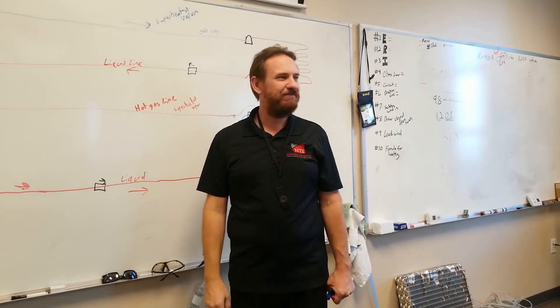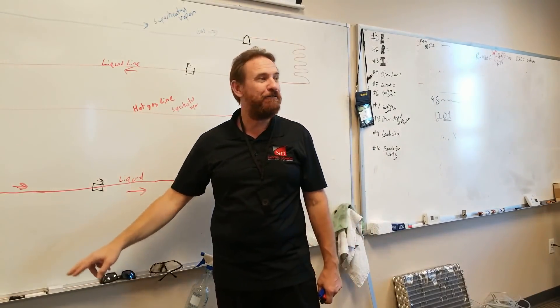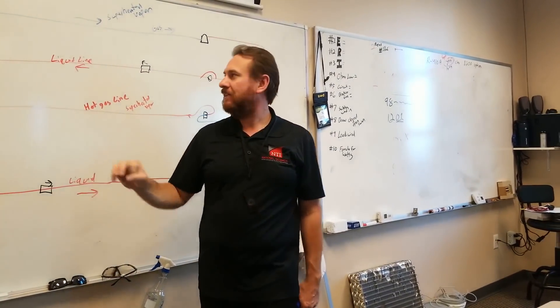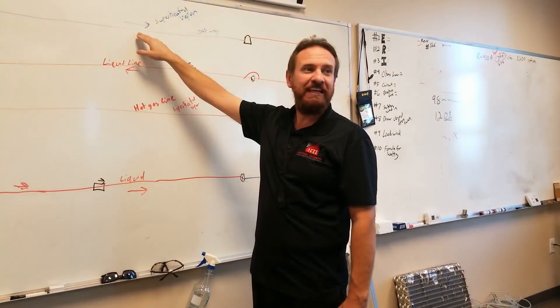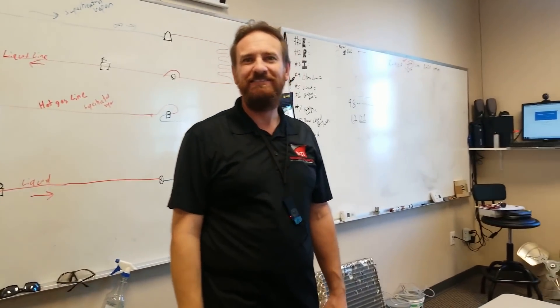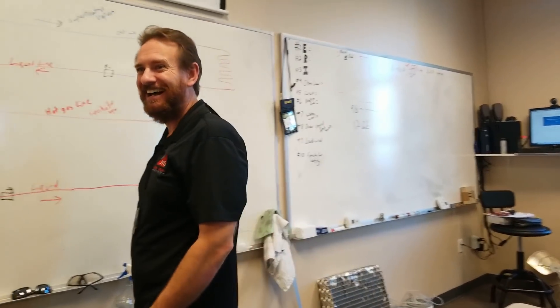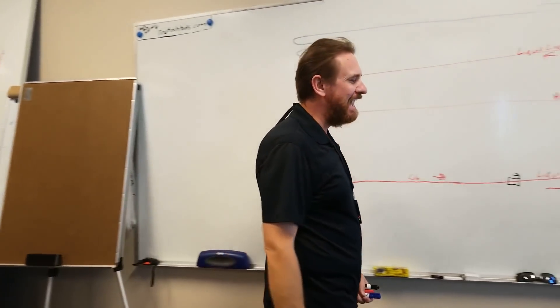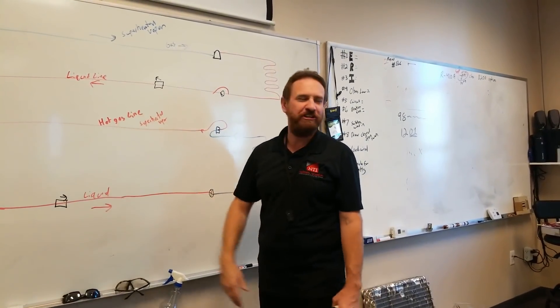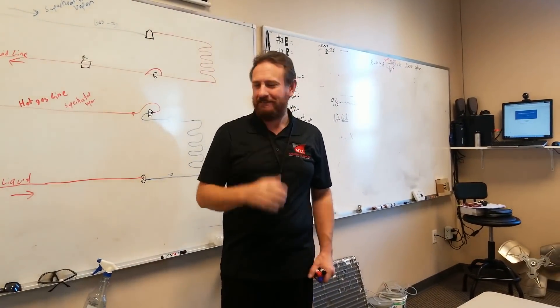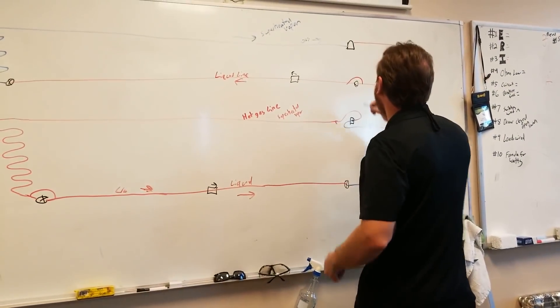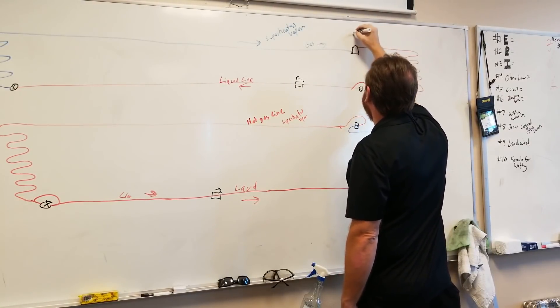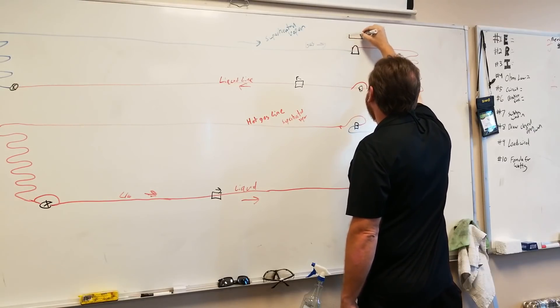Does that make sense? Isn't it cool? This line is still the liquid line — the refrigerant is flowing the opposite direction, but it's still liquid. That three-eighths line is still liquid. This bigger fat line — it's still gas here and still gas here, no matter what. There's a reason that was drilled in earlier, and this is why. So let's add some components so that we don't have to go and recover all that refrigerant and change all these components all the time. We're going to add a valve — a reversing valve — because it's going to reverse the flow of refrigerant.